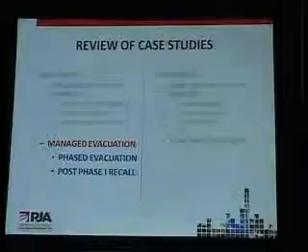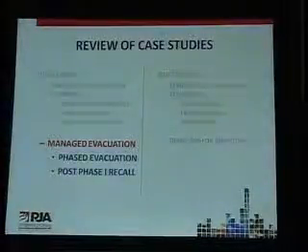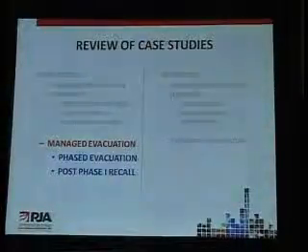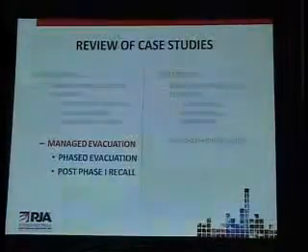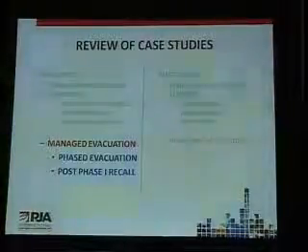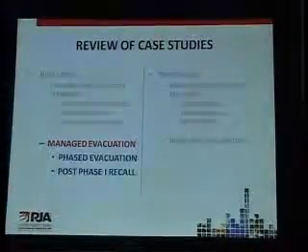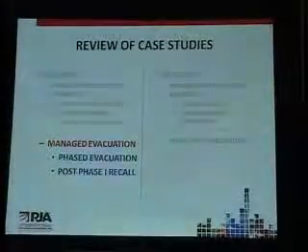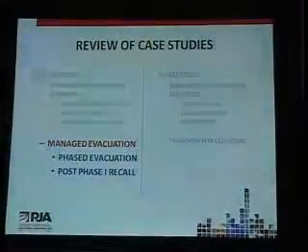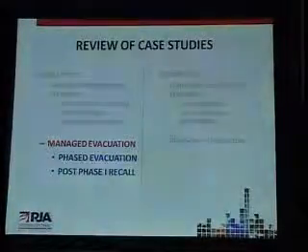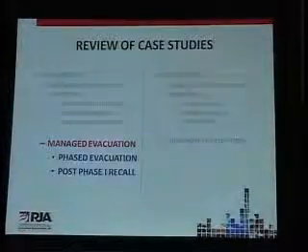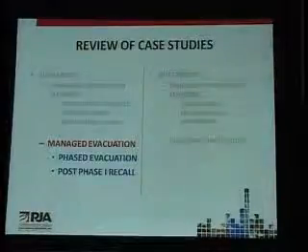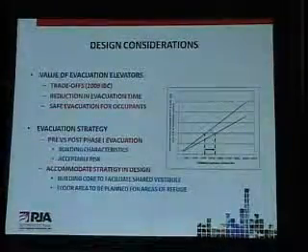And all of these case studies used evacuation after phase 1 recall has been initiated in the elevators. So if the fire alarm were to go off, elevators would be recalled. Civil defense, fire authority, whatever terminology the building uses, they can enter the building, identify where the fire is located, use the lifts to go and fight a fire, or they can prioritize going directly to an area of refuge and facilitating evacuation from that space. So this is a very big difference to what's being implemented in the 2009 IBC and NFPA.